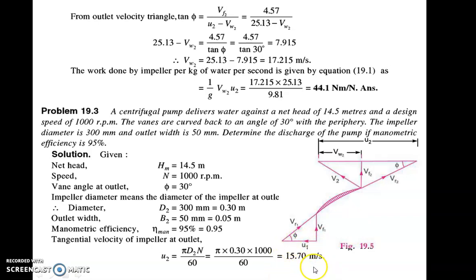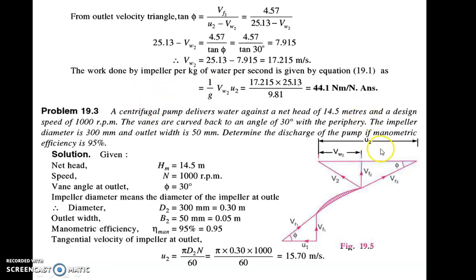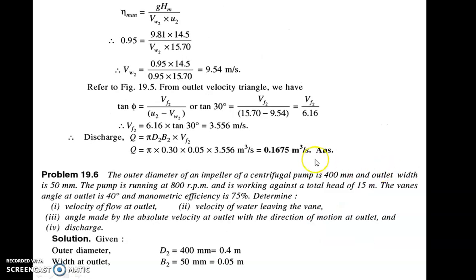From the manometric efficiency formula: manometric efficiency = G HM upon Vw2 U2. With manometric efficiency = 95%, HM = 14.5 m, and U2 = 15.70 m/s, you can find Vw2. Vw2 is found first from this formula, giving Vw2 = 9.54 m/s. Then from the outlet velocity triangle, tan(phi) = Vf2 upon (U2 minus Vw2). So tan(30°) = Vf2 upon (15.70 minus 9.54) = Vf2 upon 6.16. Therefore Vf2 = 6.16 × tan(30°) = 3.556 m/s.